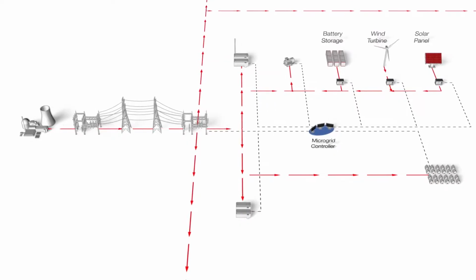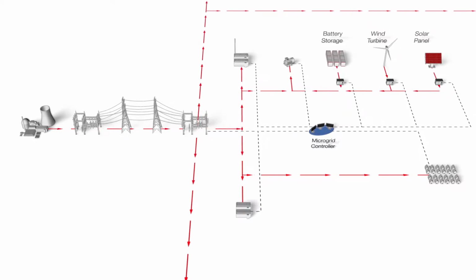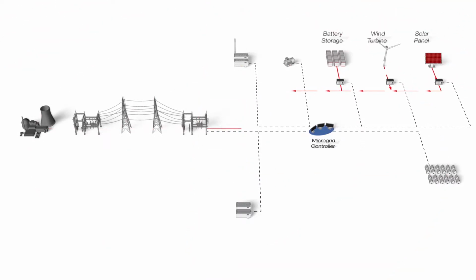I am doing great. I'm so glad you're here. It's very special. And I want to go ahead and get started with asking you what are the major challenges of integrating distributed energy resources in DC microgrids? So let's say we have multiple loads and sources connected to a DC microgrid, and let's say one of the load or one of the source goes into a fault condition. In that case, your controller will see that impact of that fault with the DC voltage at the point of common coupling. So that is one example where the controller must know what to do.